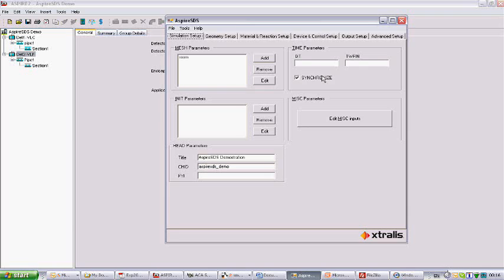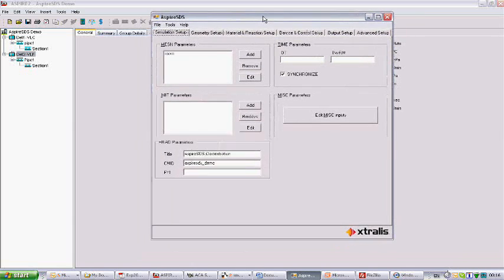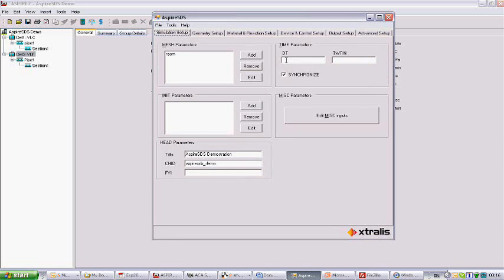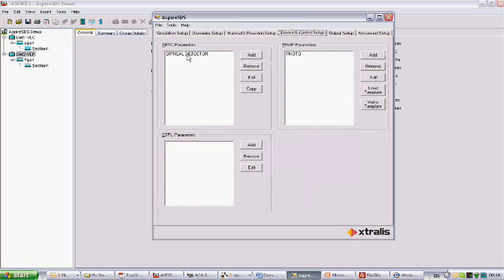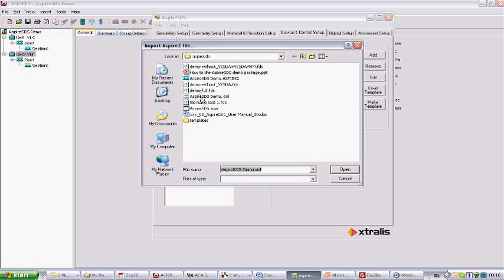The software that we actually use to import the data into FDS is of course the new AspireSDS tool. We actually use this tool to create the model that I first showed you, including the main room space and including the 5 cabinets in the space, the fan, and define the positions of the door and the burner, etc. We also define the position and the characteristics of the optical detector. And what we need to do now is to import the VESDA detectors from the Aspire 2 that we created in the background. And that's simply a case of importing the Aspire data that we saved earlier.